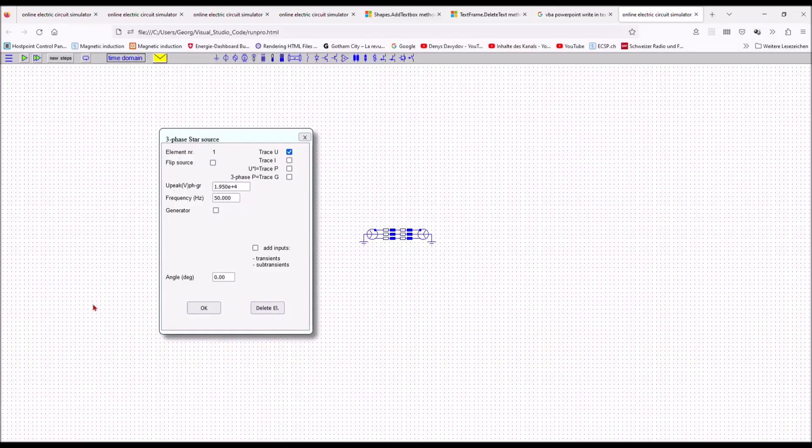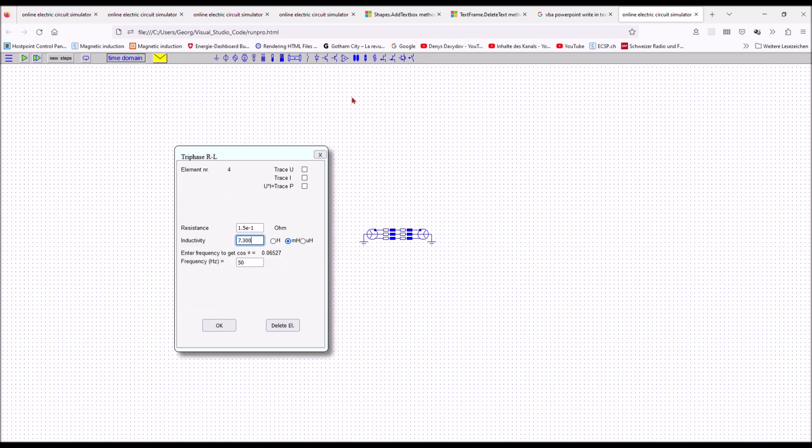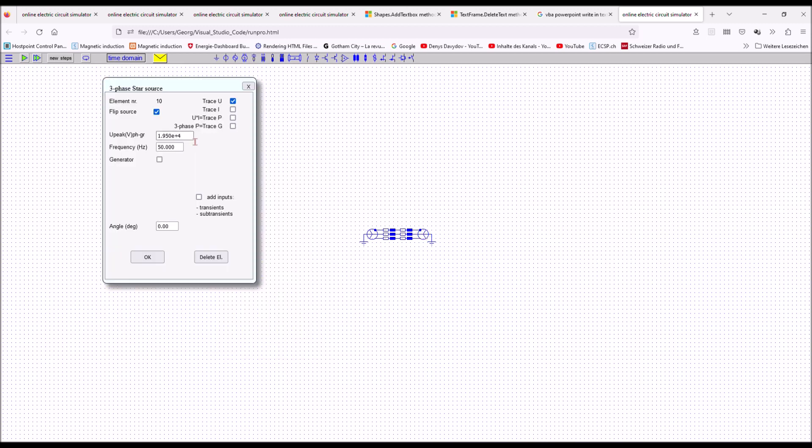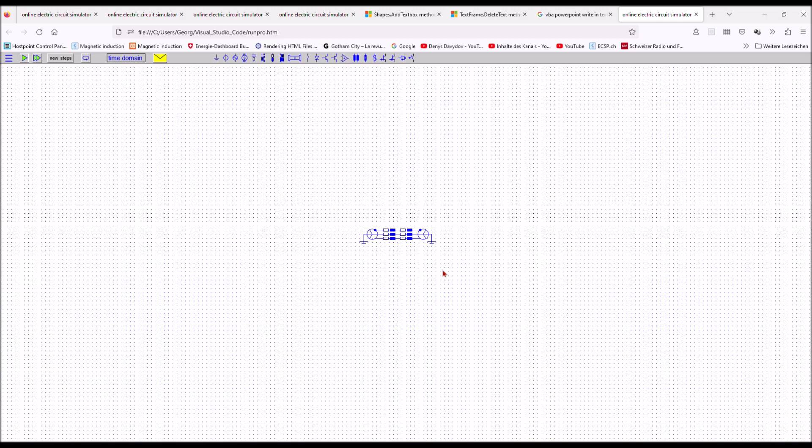What you get as a result you see it there and we will now implement these results into our simulator. The voltage source part of the 24 kV generator has a peak phase to ground voltage of 19.5 kV. I enter the results of my calculations for the two synchronous reactances of the generators. To begin with we said that the generator on the right side has no magnetic field in the rotor, thus the induced voltage is zero.